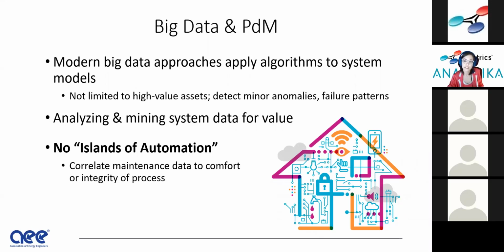So now we can apply predictive maintenance to even small endpoint devices, such as VAV boxes, for example, process utility connection points. You really can scale AFDD down to detect even minor anomalies and failure patterns. This allows you to determine the assets and operational processes that are the greatest risk of failure. Sometimes not always the highest savings, you know, but important for other reasons. Is this a lab space? Is this a manufacturing space? So really important, this piece, the modeling, the topological modeling, and the fact that we can scale down and scale up, of course, to multi-building sites.